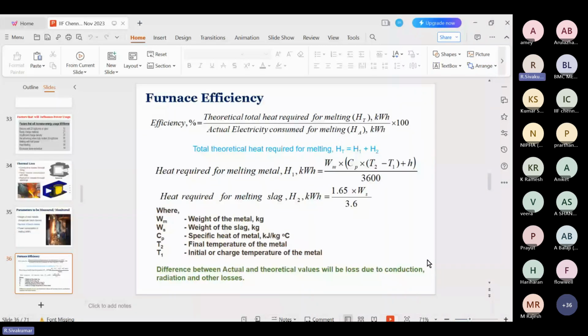So how do we arrive at the furnace efficiency? This is the formula. Efficiency is basically output by input. So the efficiency depends on the theoretical heat required for melting divided by the actual electricity consumed for melting. The theoretical heat is in two parts, H1 and H2: the heat required for heating the metal and the heat required for heating the slag. H1 is the major thing.